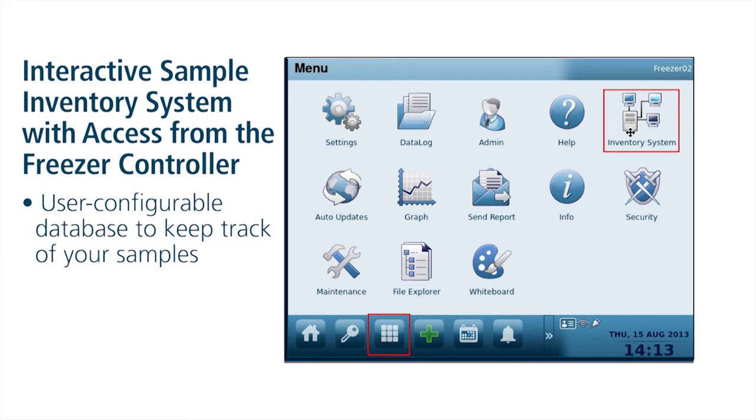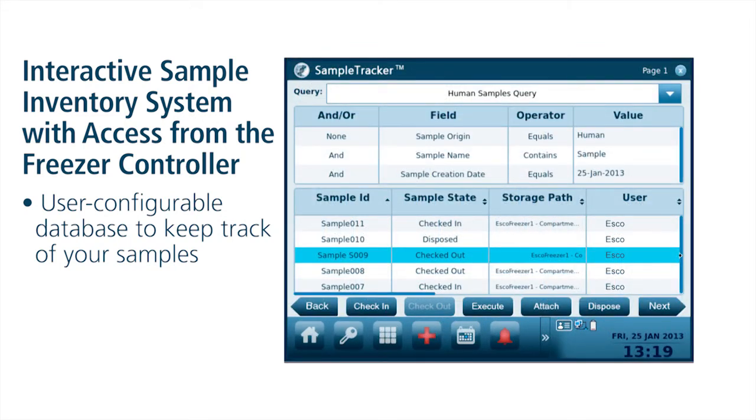Database searches can even be performed using the Lexicon 2 Alto Platinum Controller. Input a user ID or scan a report with a barcode scanner on the freezer, and the Alto Platinum Controller will display the sample location right on the freezer screen. If you think you know where your sample is, enter the sample ID after retrieval to confirm the sample. If it is the right one, great. If not, the freezer screen will show you the location where to return the sample.